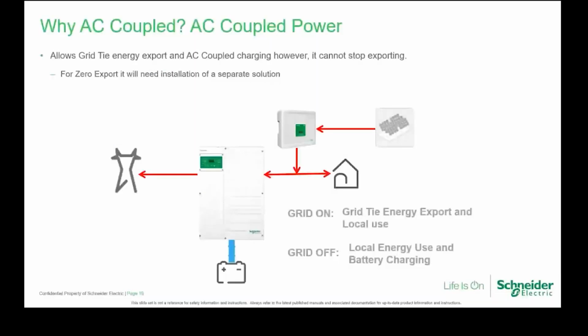Okay, it allows grid-tied energy export and AC coupled charging. However, it cannot stop exporting. As I said before, once you hook it up to the grid, you've got a PV inverter, it will then try to export out if there's any excess energy. You will need to put in a zero export solution. So when the grid's on, you have grid-tied energy export and local use. When the grid's off, you've got local energy use and battery charging.